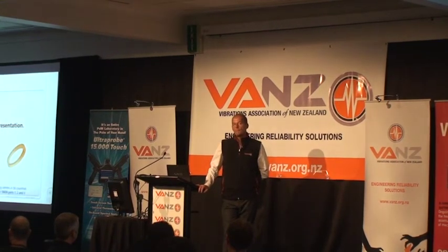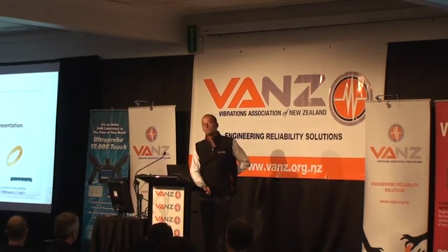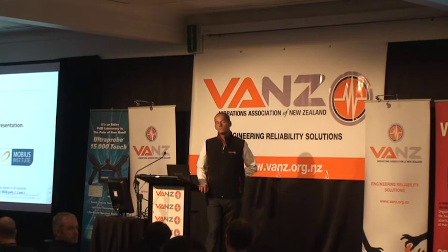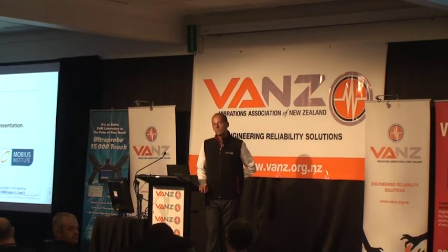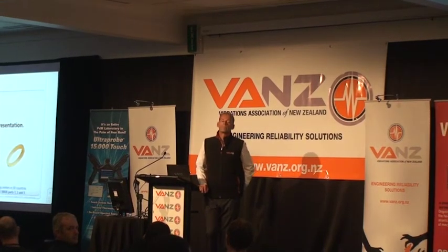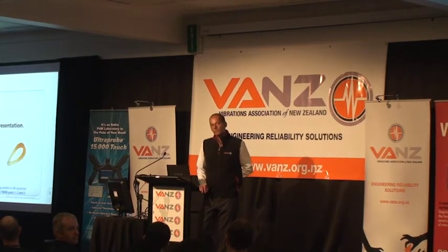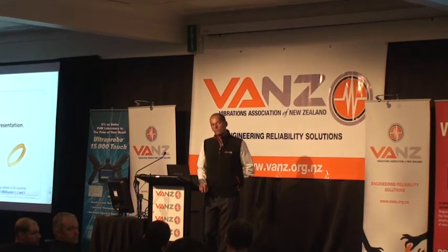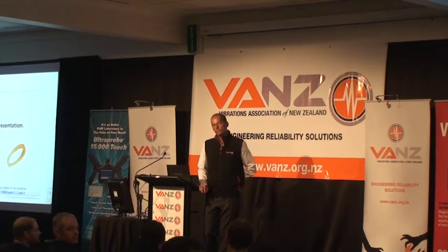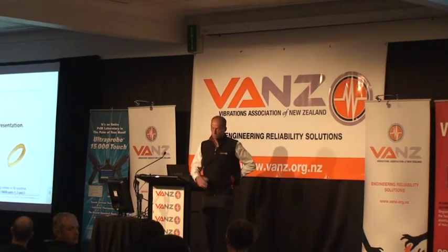Yeah, I played around with them and I think the main issue with high-speed machines is that the frequency, you don't get much displacement for the vibration frequency. Yeah. The displacement for very high velocities is quite low, and that's the danger, because velocity is actually a measurement of the energy. Yeah. Well, there is that too.